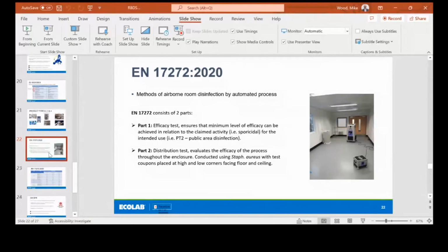You can see the enclosure in which we did our testing there — that's a 78 cubic meter enclosure. What happens within the test is that carriers containing microbiological organisms, depending on the claims you want to make for your technology, are placed out in various locations, facing away from the generator.